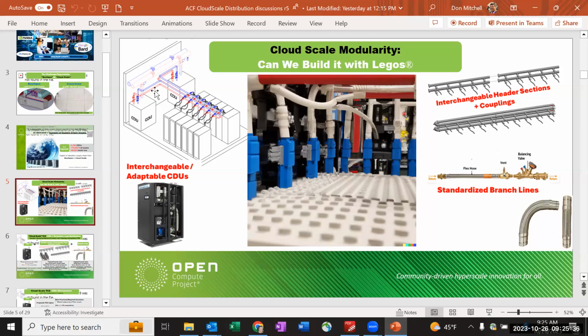So say we have an existing, completely air cooled installation, and they're at 1.5 kilowatts per server, and they start swapping them out for 5 kilowatt servers. You can't air cool that, so the only way to cool it is cold plate. Now you've got to install something like a CDU or a rear door heat exchanger to dump the hot coolant into the atmosphere.